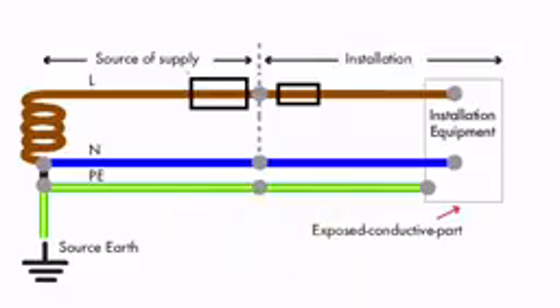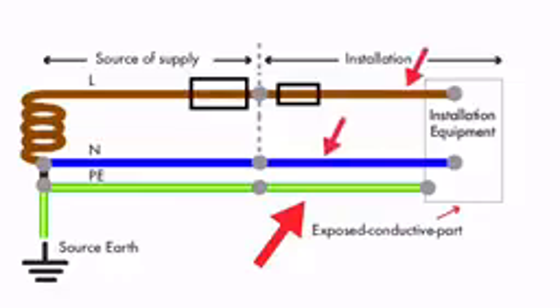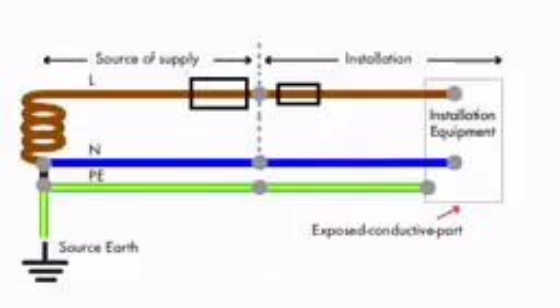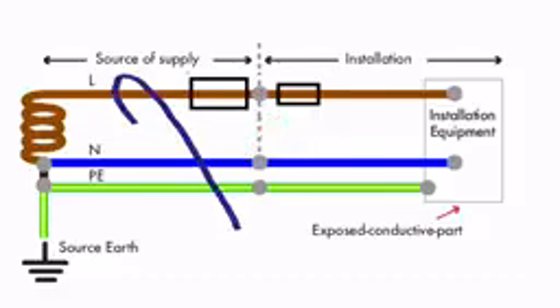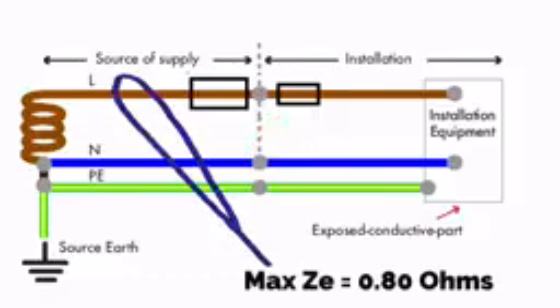The installation shown on the right hand side could be a lot shorter in length than the supply authority's cable, comprising of a line, a neutral and a CPC within the circuit. As with the supply authority side, we have a separate line, neutral and CPC in circuit. The fuse for this circuit will not be 100 amps, but considerably less, maybe 20 amps, and would be located within the distribution board itself. The maximum external earth fault loop impedance for a TNS earthing arrangement is 0.8 ohms.